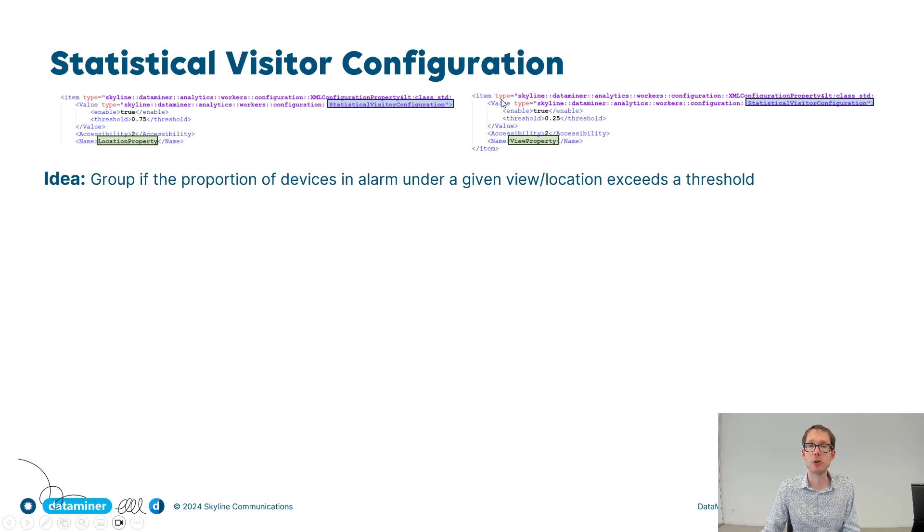There's a similar idea for the view property. Here, the threshold by default is set to 0.25, but you can tweak and change it how you want. What does this mean? Well, it means that we will group alarms on devices in the same view if at least 25% of the devices in that view have alarms. That's the idea.